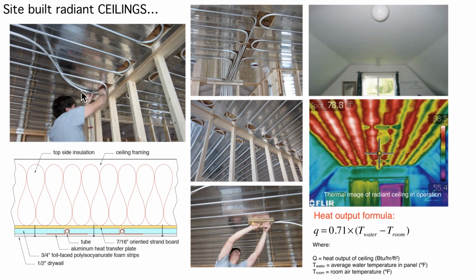This is 1/2-inch PEX aluminum PEX tubing. And what he's doing right down here, he's using a wooden float to just press that tubing up into those plates. And there's no need for any glue to hold it there. Those plates are shaped so that they do capture the tube when you push it up in there. So when it's all done, at least when the tubing's all installed, all the tubing's up here. Here's where he's brought several circuits together, brought them over to an interior partition, and then drilled down through there.